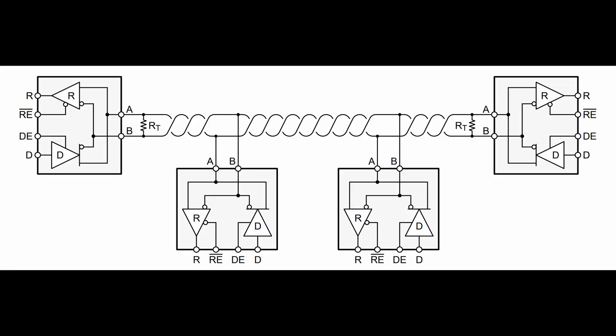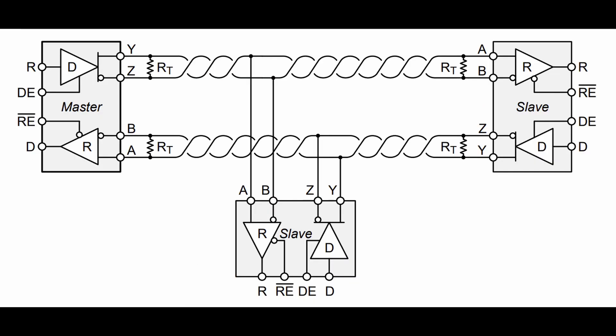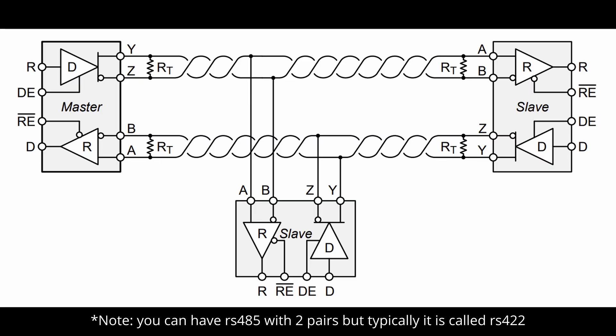Each channel can be configured for one of three modes. RS-485, which is a single pair receive transmit. This is nice since only one pair is needed and you still get bidirectional data, just not both directions at once. RS-422, which is two pairs, one for receive and one for transmit. This lets you do both at once at the expense of needing to run an extra pair.